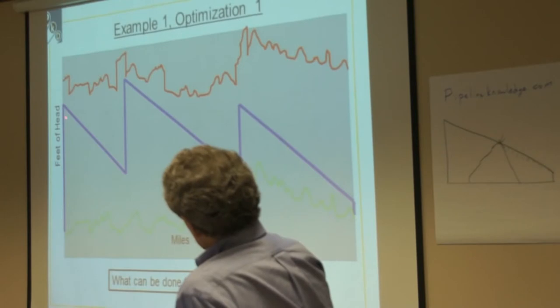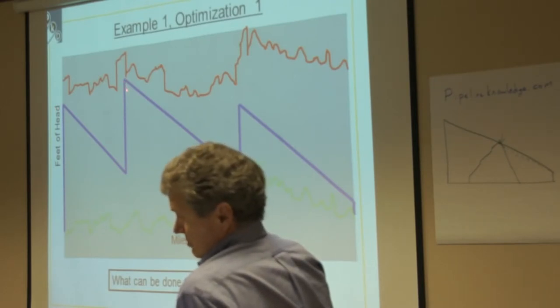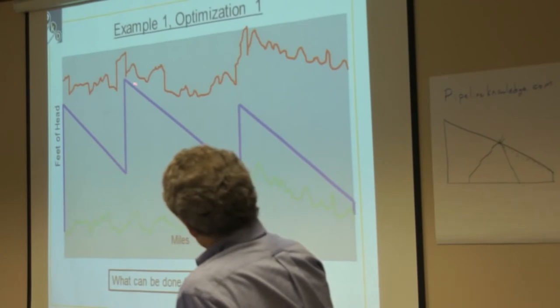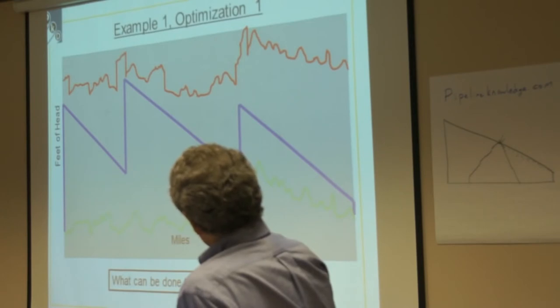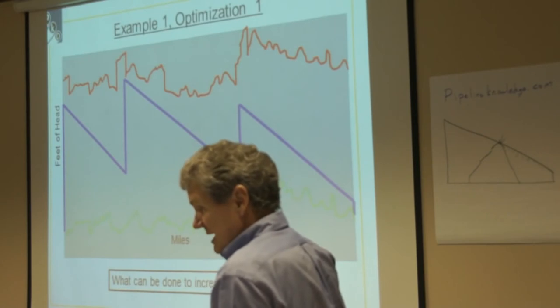If you're looking to increase your rate, you're going to have more pressure loss between the pump stations. So can you discharge at a higher pressure here? Yes. Can you discharge at a higher pressure here? No. Can you discharge at a higher pressure here? Yeah. So what you might do is, you might increase your pressure here, let this come down a little bit so you can go up, have a steeper gradient there, then discharge higher here, have a steeper gradient there. Now, do you have the pump units to do that? Don't know. All you're doing here is looking at this. There's a lot of information you don't have. You're just kind of looking at it and saying, where would I look first?